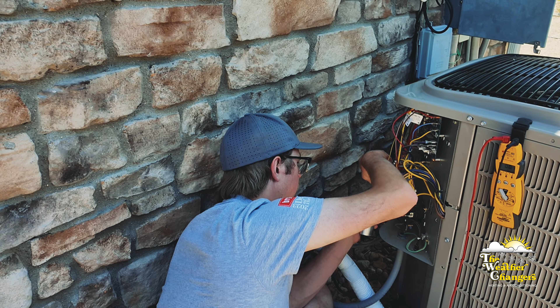We're going to check inside the condenser here to make sure the electrical components are all within spec and look right. We have our capacitor here. We're going to be checking that, making sure that that's within spec. And we're also going to be inspecting this board and making sure everything is plugged in properly and there's no burn marks.